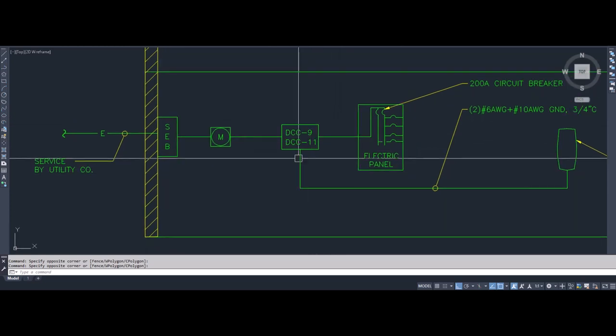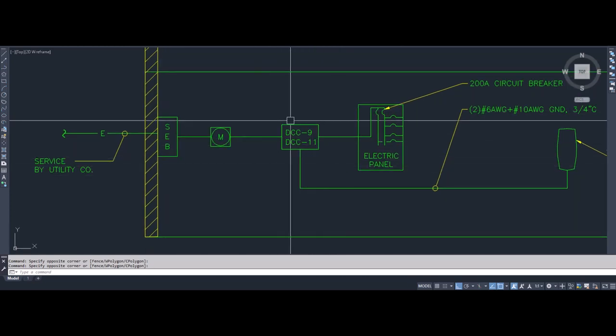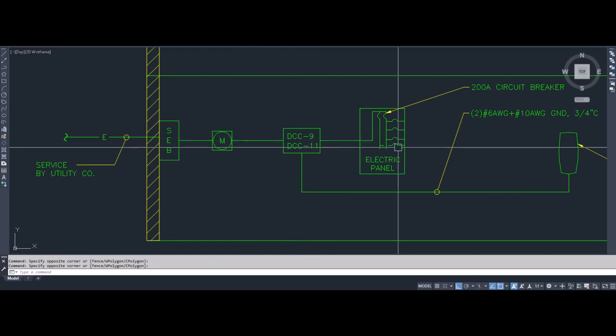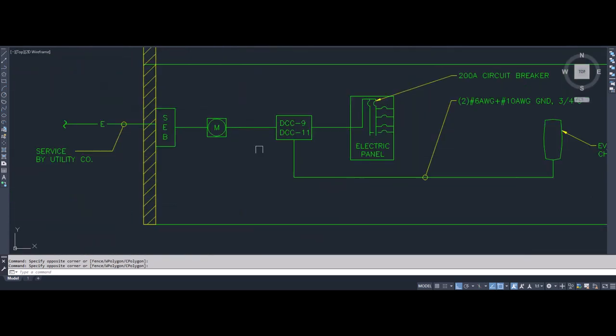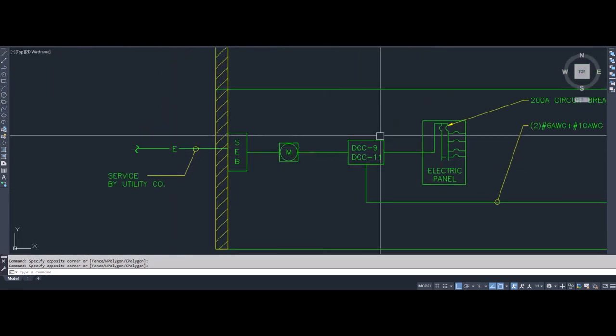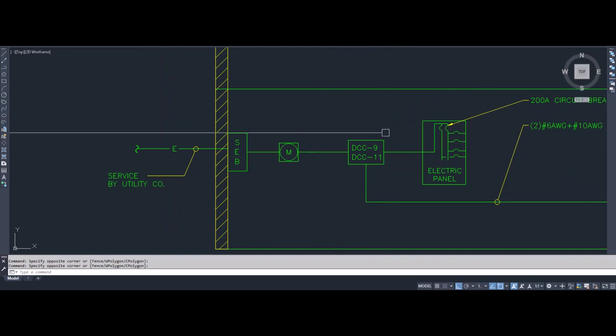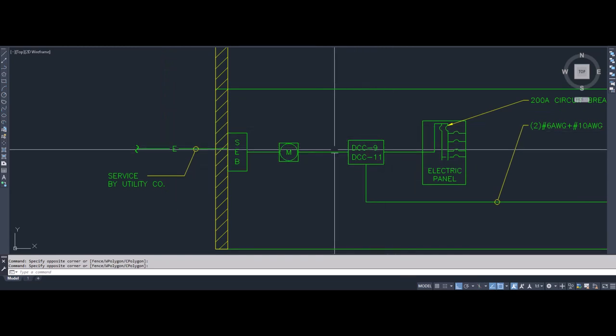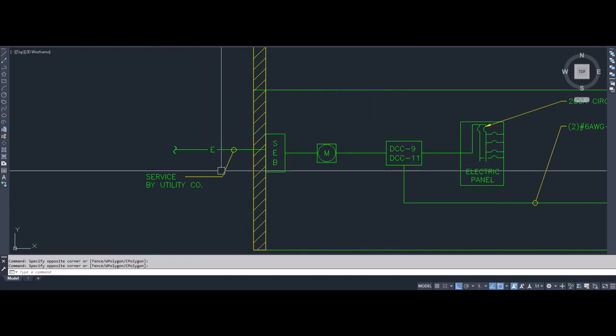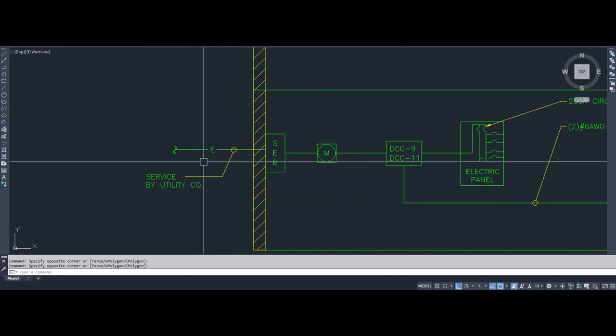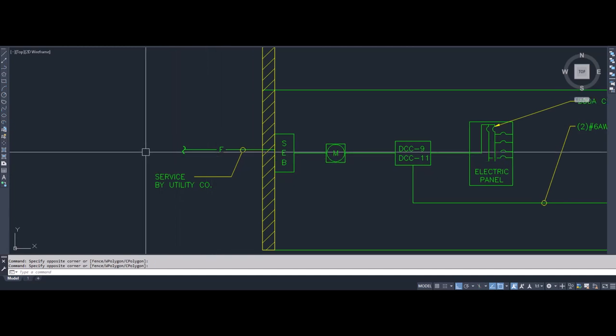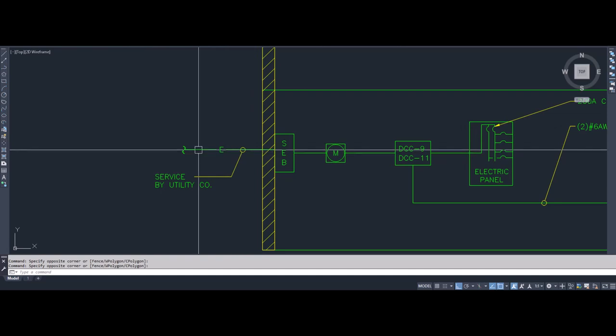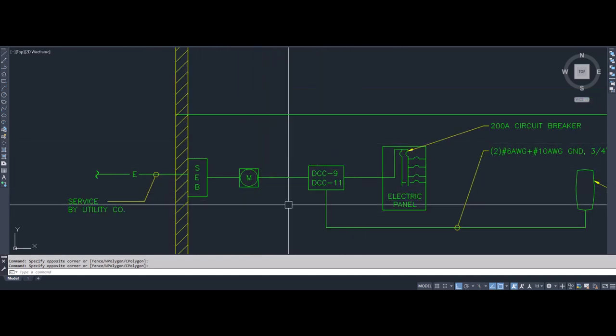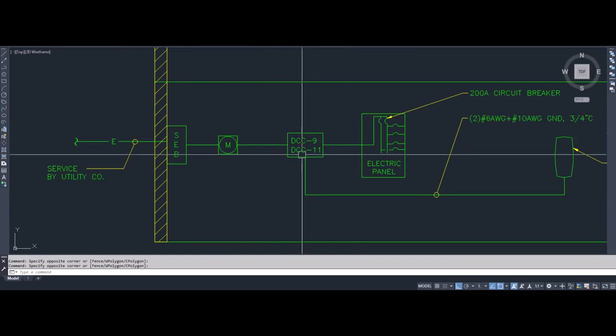If you were to do some maintenance work on this system, then how would you shut it off? There is no main disconnect here, like in this example. So to cut off power, so you can do some sort of repair work on this or just replace it, you would have to ask the utility company to shut off the power. And they're usually not very quick. So that might take a little bit of time and it might not be a very ideal situation. So I wouldn't recommend installing the 9 or 11.